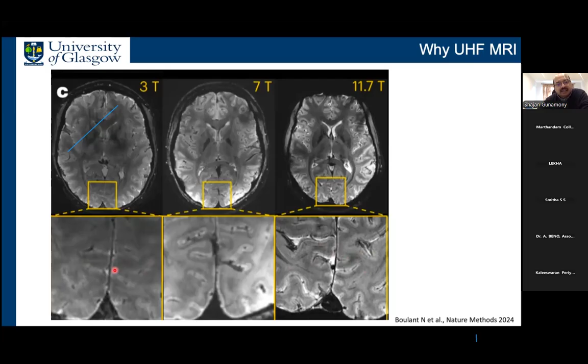Okay, so even in this study, the conclusion was the same, that the gain in SNR is more than linear with respect to field strength. And this is a figure from a recent publication from the Neurospin group, where they scanned the same volunteer in 3 different scanners with comparable imaging parameters. And you can see the level of detail that you get at 11.7 Tesla compared to the clinical scanners, 3 Tesla and so on.